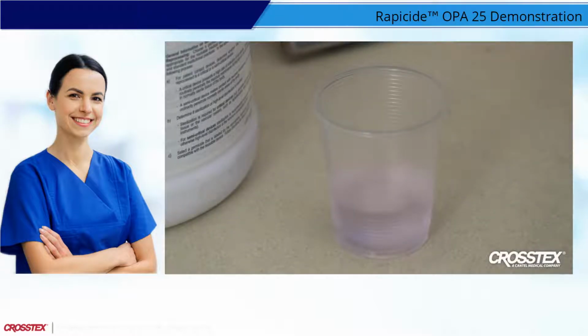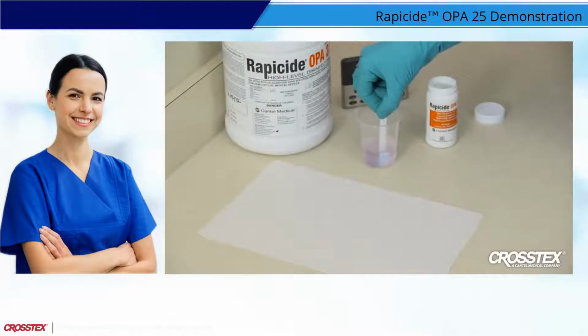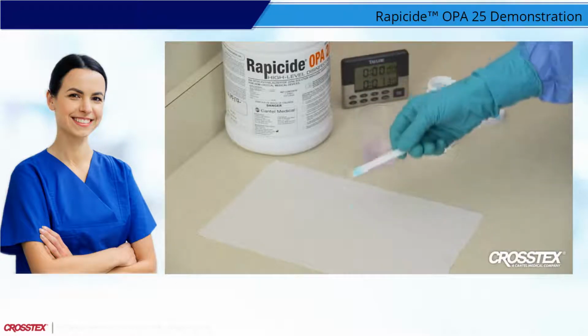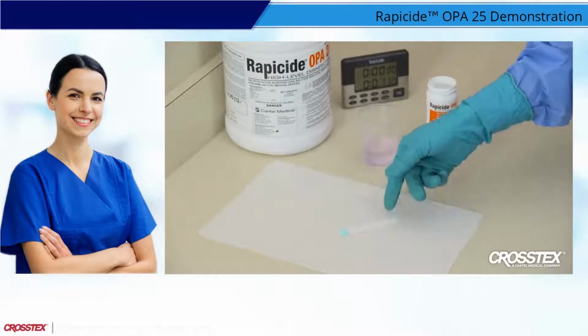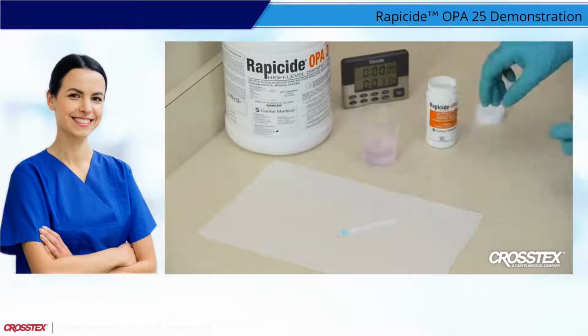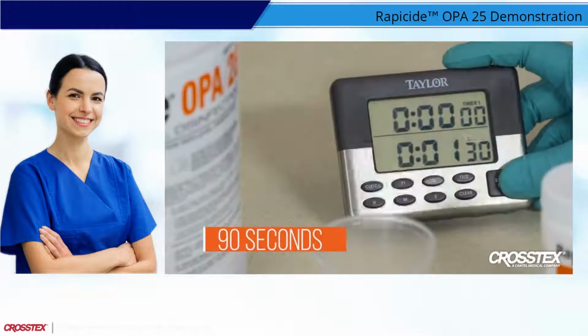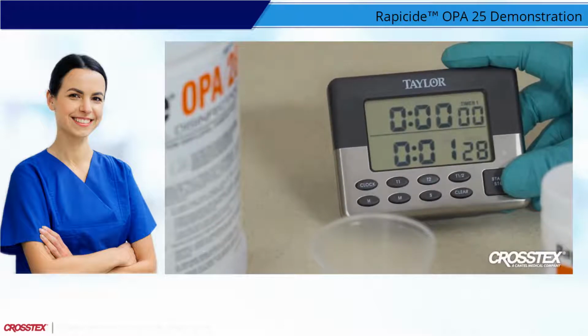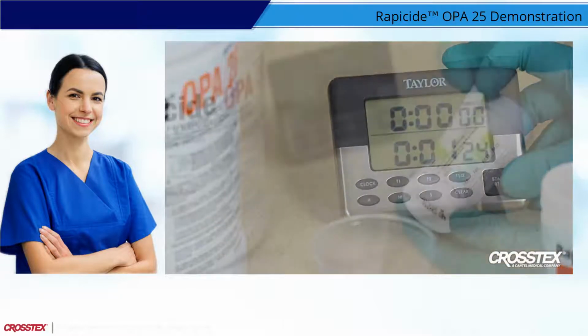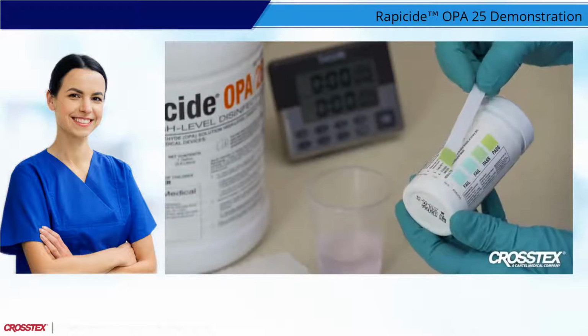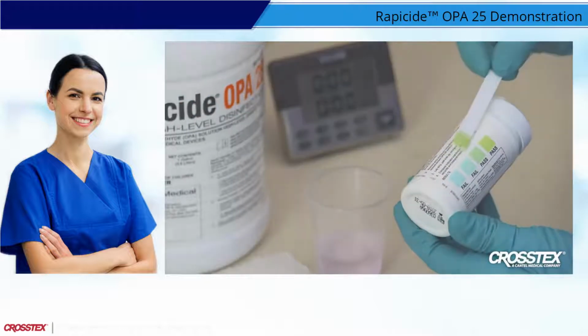Remove the strip and touch the long edge on the paper towel to remove any excess Rapicide OPA 28 HLD solution. Lay the strip pad side up on a paper towel and start a timer for 90 seconds. Compare the indicator pad to the color blocks on the test strip bottle at exactly 90 seconds and interpret the result. The color of the indicator pad will be green when the concentration of OPA is above the 0.35% MRC.